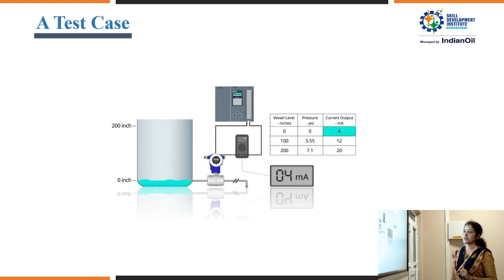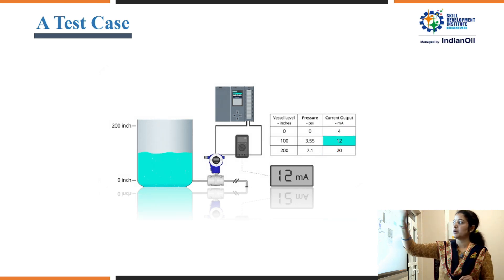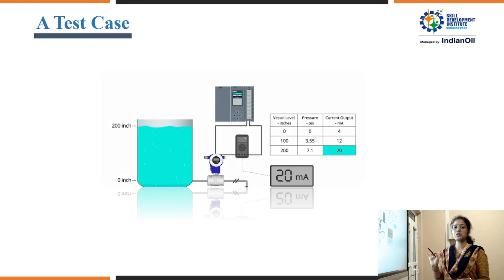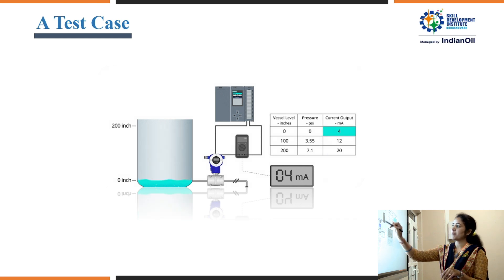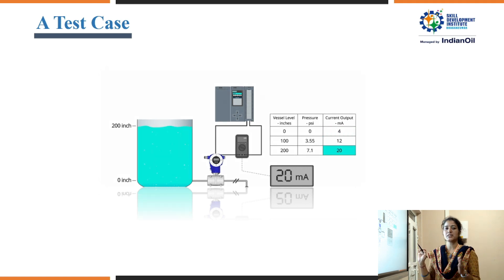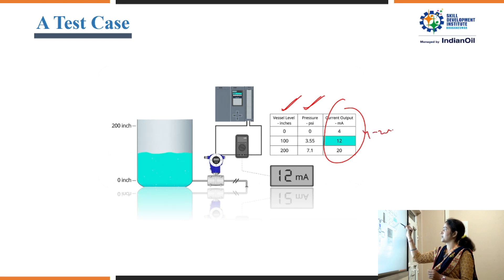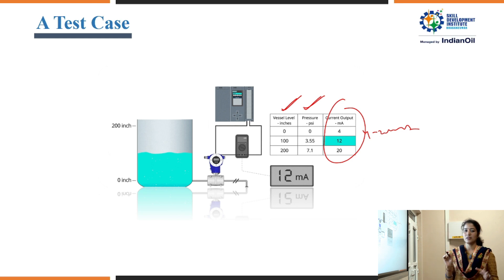As a practical example, consider a tank being filled with liquid. The level increases from zero to 200 inches, and a pressure transmitter checks how much pressure builds as the liquid level rises. Pressure is a physical, non-electrical quantity that must be converted to an electrical quantity when it reaches the controller — this conversion is done by a transducer, which converts the non-electrical quantity to an electrical current in the range of 4 to 20 mA, and that signal is received by the controller to complete the process.